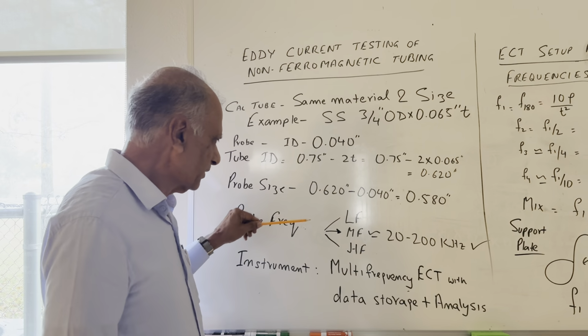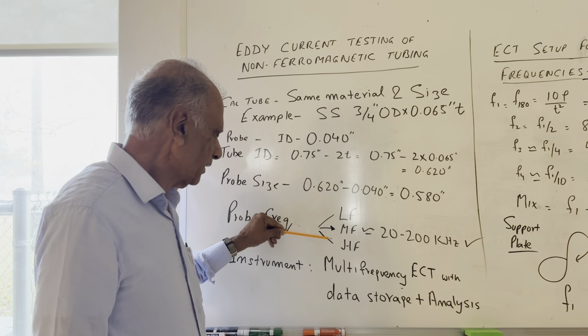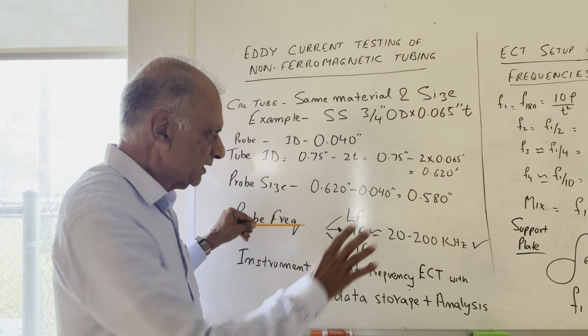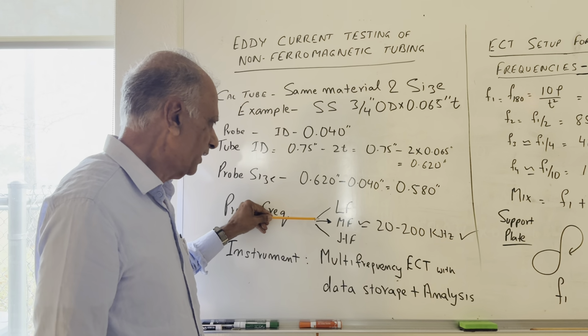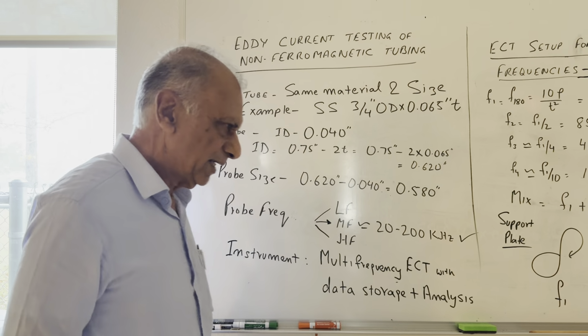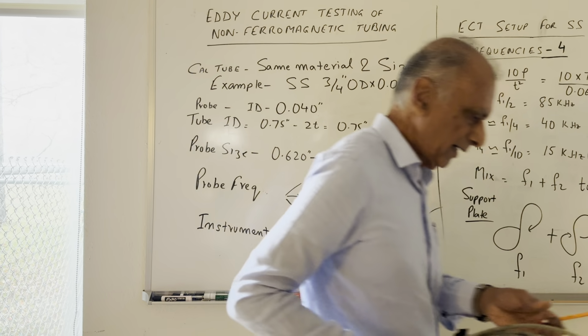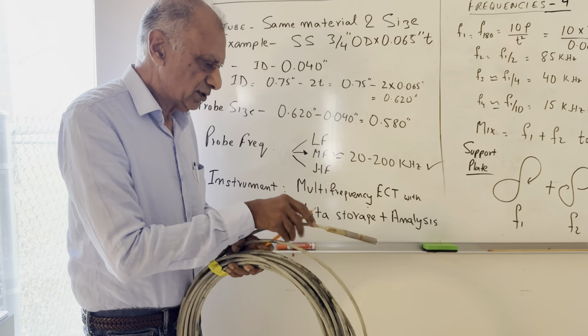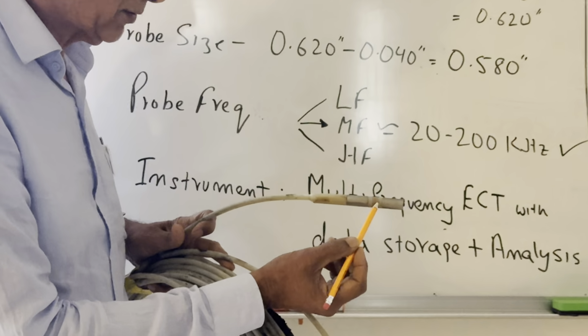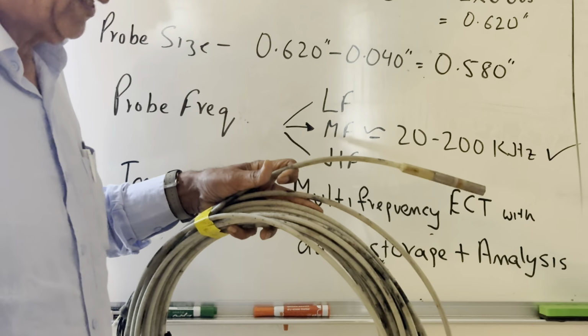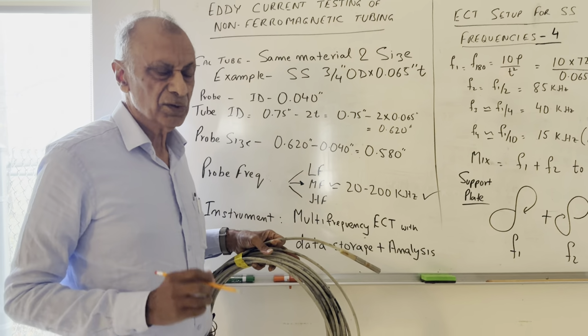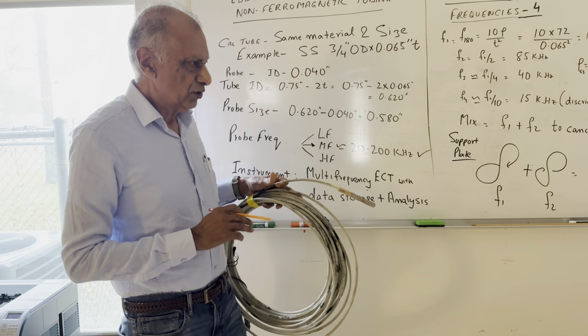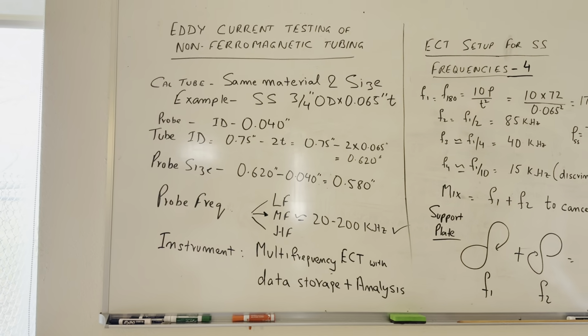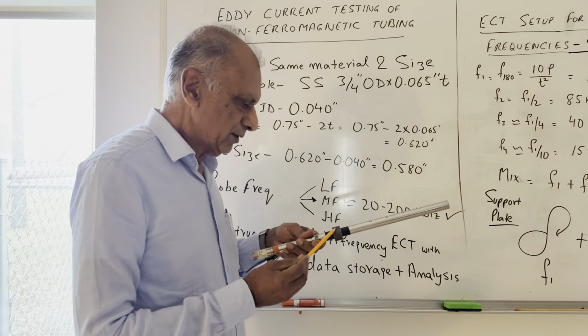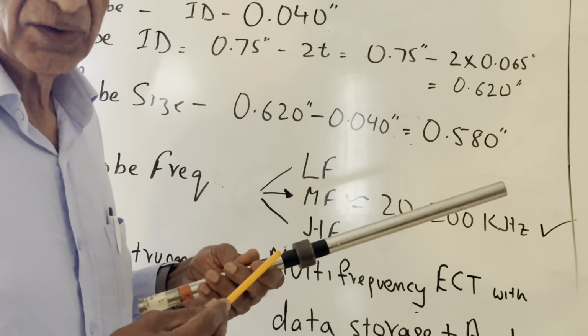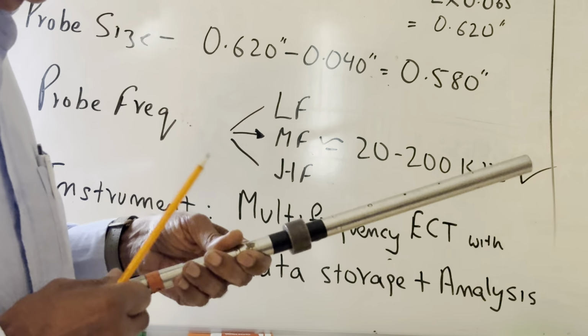Then there are 3 types of bobbin probes: low frequency, medium frequency, and high frequency. In this case, the frequency when I calculate will come out to be around 100 to 200 kilohertz, so we will use a mid-frequency probe with a diameter of 580. Again, I'll show it to you. It's right here, and that's what it looks like. It has 2 coils which can operate in the differential mode or in the absolute mode. The probe length is about 50 to 60 feet, so that it can be inserted into the heat exchanger tube. In this calibration tube I've put a support ring, because we have supports in the heat exchanger, to produce a signal from a support.